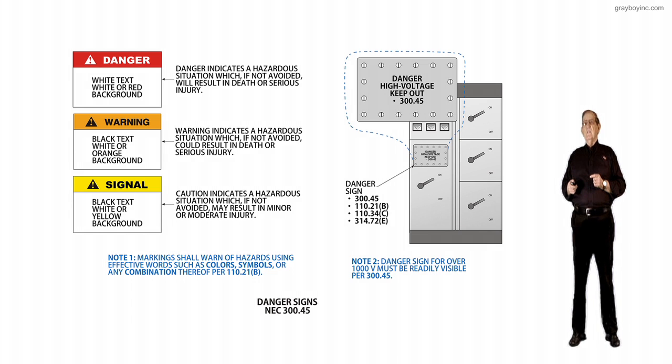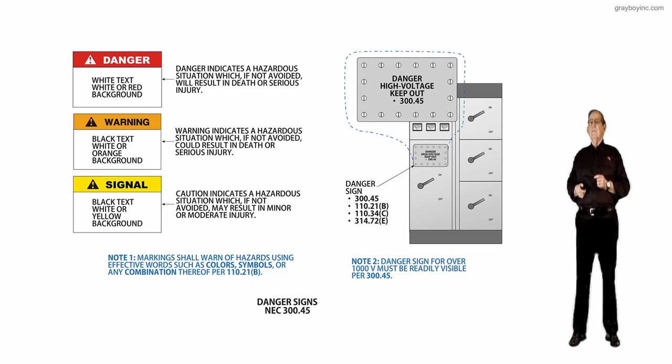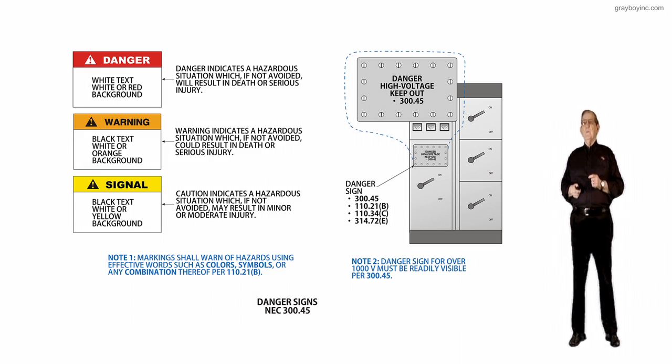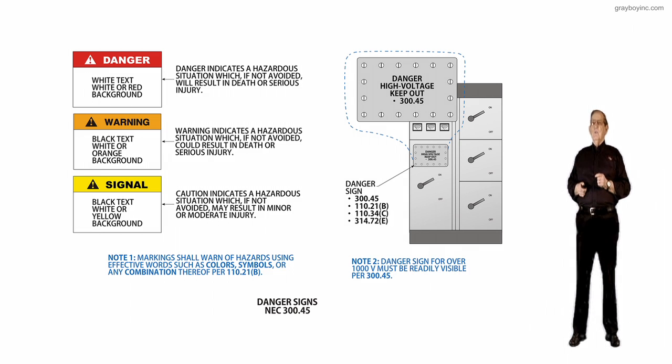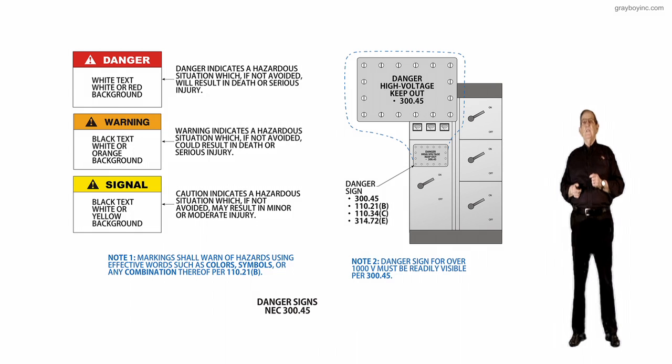And notice the danger sign, secondly, that I'd like to call out, is also listed in 300.45, 110.21(B), 110.34(C), and 314.72(E), as in Ed. And then, thirdly, I would like to call out the red. That's a Z535.4 requirement, and that's immediate danger.